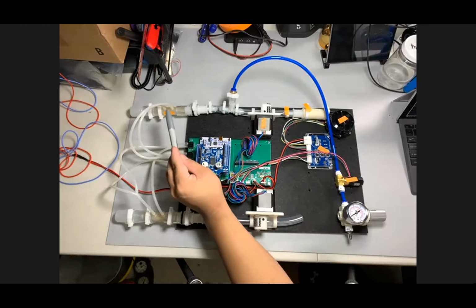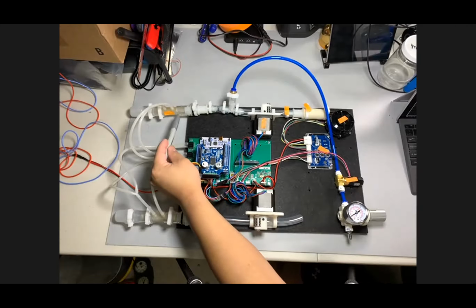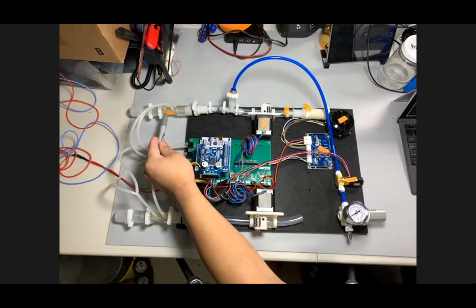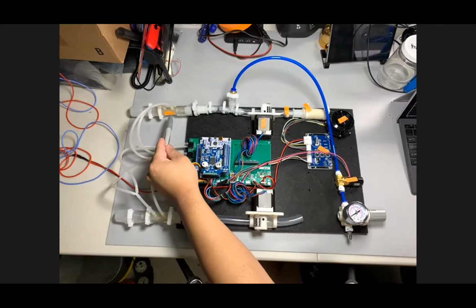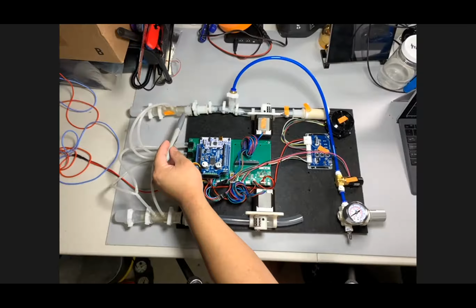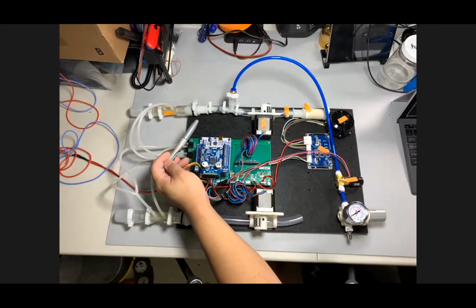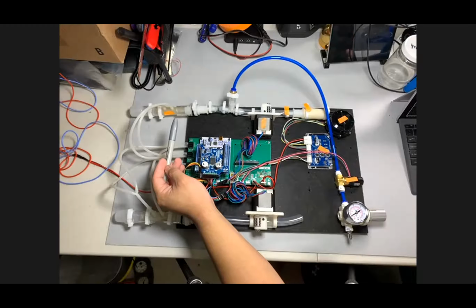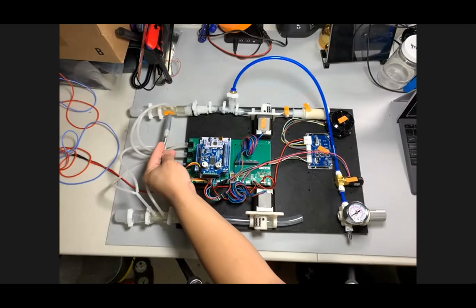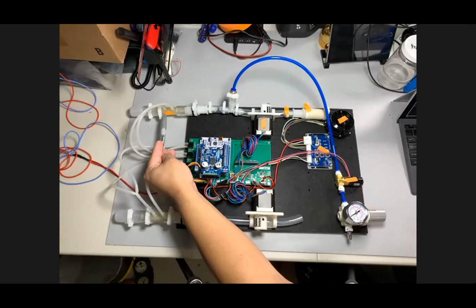The reason we don't tap off of this inlet here is that when you have a venturi, there's a drop in pressure across the venturi, right? And the venturi works by creating a vacuum on one side of the differential pressure sensing that is dependent on flow. So there's a constriction in the venturi. I know a lot of you know how venturis work. I'll just go over it quickly for those who aren't familiar with it. There's a constriction. The air accelerates as it passes through the constriction, which creates a vacuum in the line. And so because of this constriction, there's a pressure drop also across the venturi.